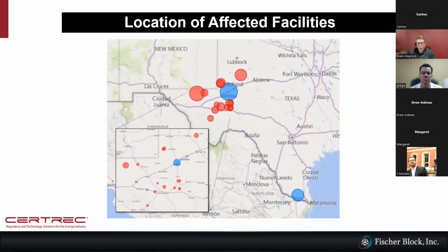So closer in, typically you have a greater effect, especially with voltage issues. And that's really what happened in this particular event: there's a lightning arrestor in the 2022 event that failed, causing a low voltage on one of the phases. As a result, the IBRs, as fast as they are, will try to bring that voltage back up to where it needs to be. And when the fault was cleared within a few cycles, voltage on the grid was restored to normal. However, the inverters were not necessarily quick enough to bring that voltage back down as output from the inverter, and it may have tripped on overvoltage, but there were also some other events too.